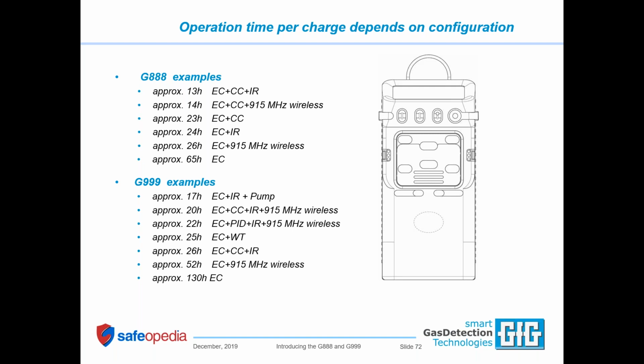With the 999, everything is doubled. So a G999E with only electrochemical sensors gets up to 130 hours of continuous operation. If you leave the pump turned on continuously in a standard 4-gas instrument that includes an IR LEL and an EC sensor, you get about 17 hours.